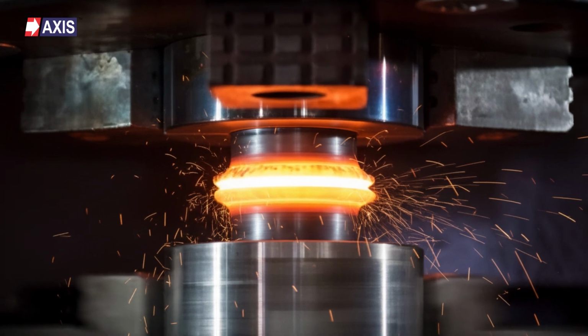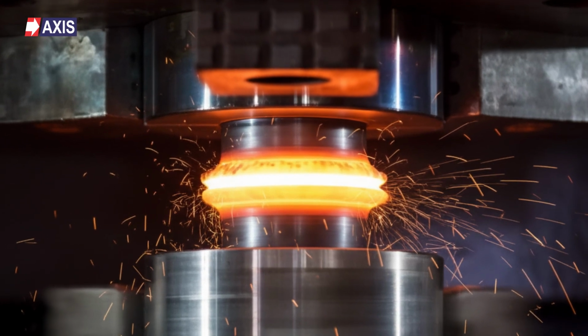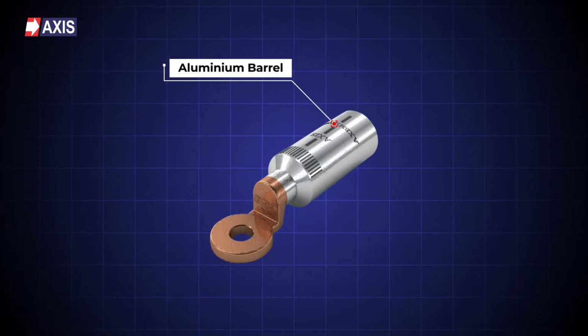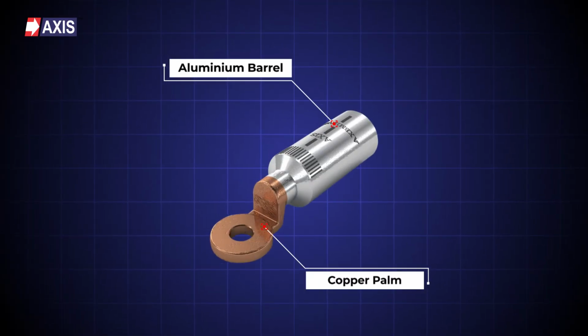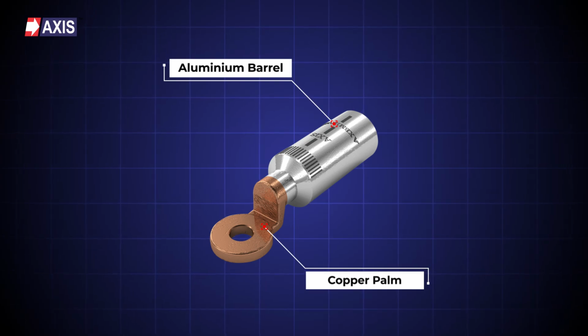A bimetallic lug removes the problem. The friction weld creates a bond at the atomic level between the aluminium barrel and the copper palm. The aluminium meets aluminium on the cable side and the copper meets copper on the bus bar side. No dissimilar metals touch each other anywhere in this connection.